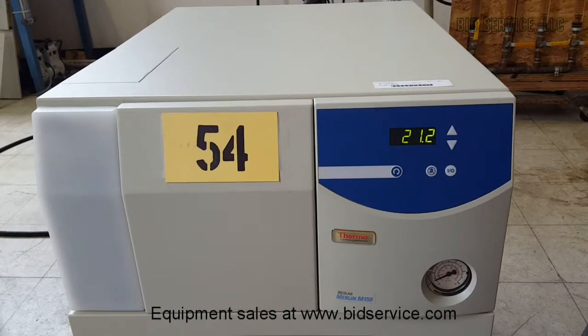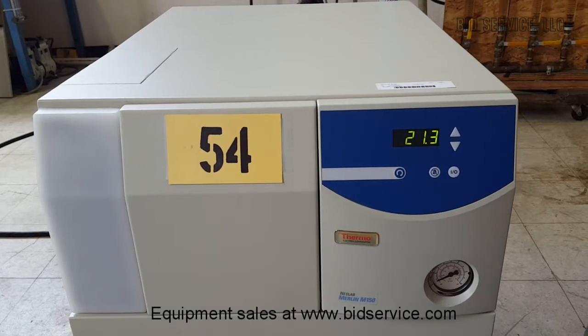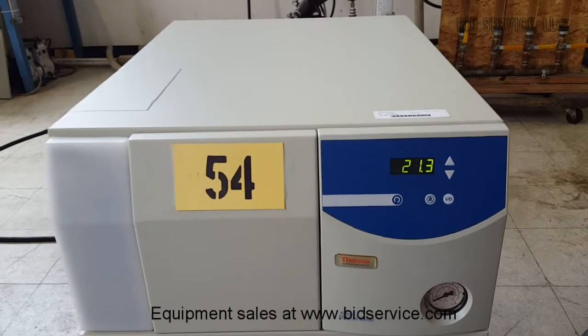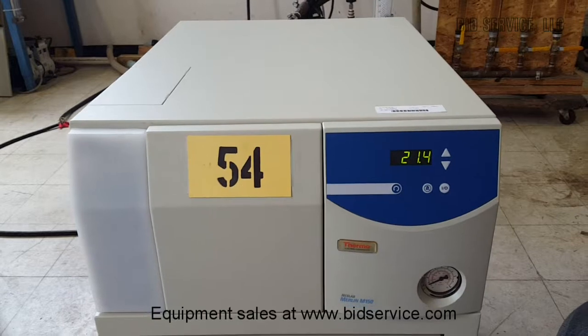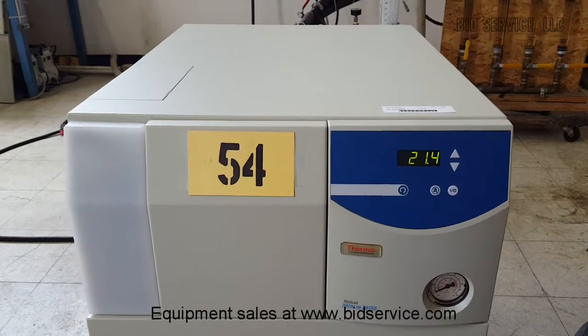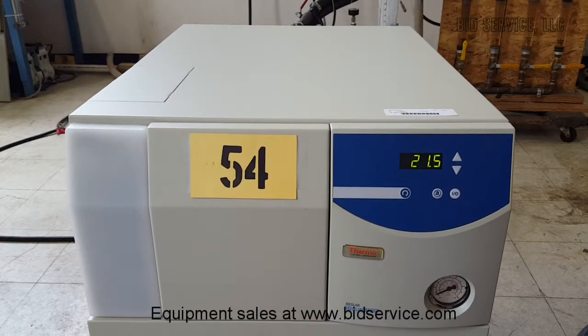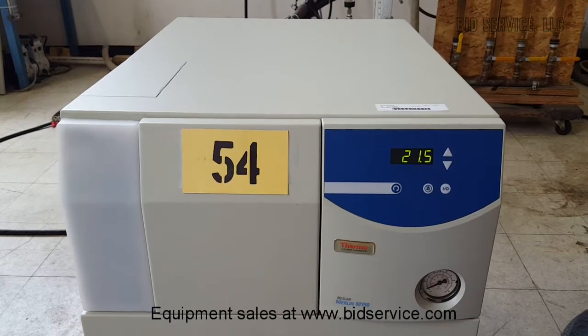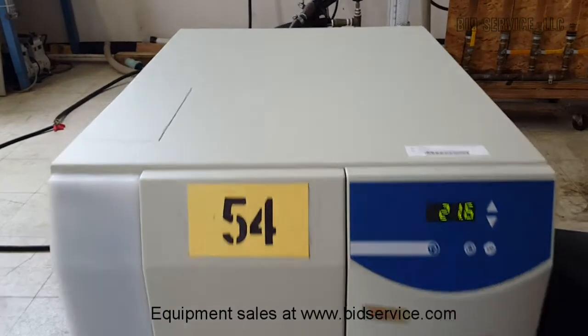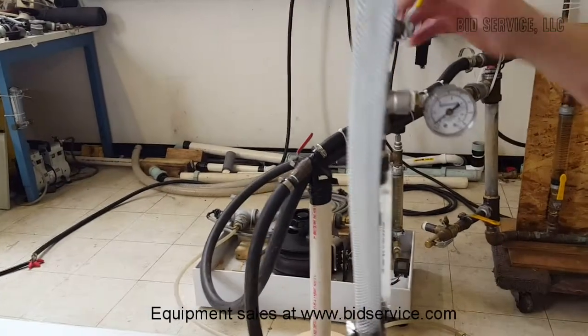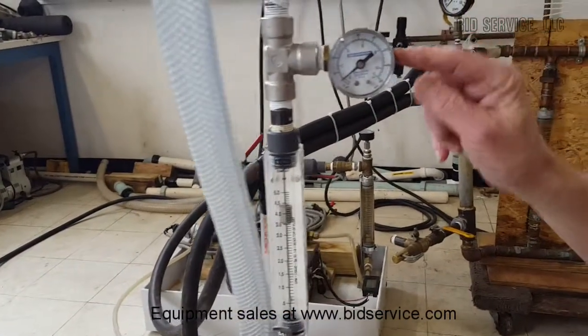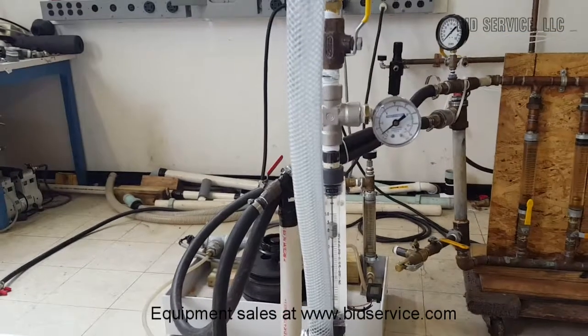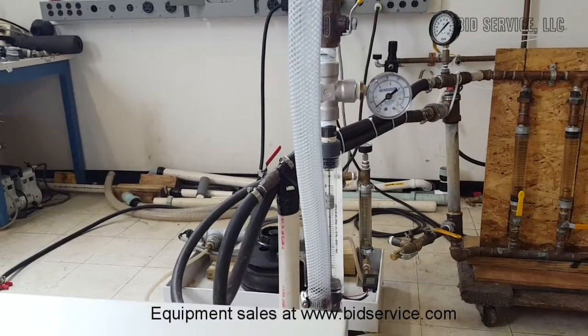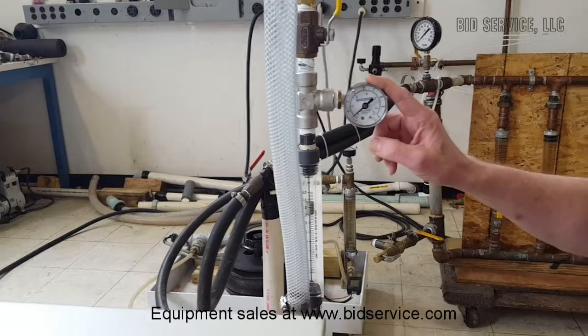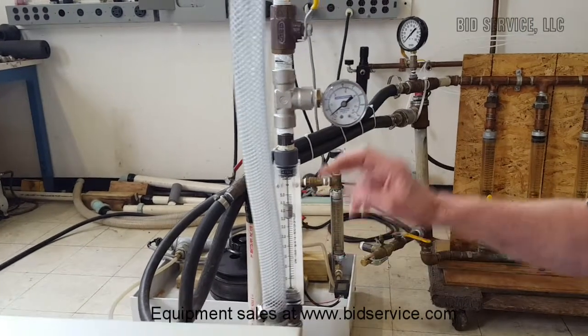So while we're waiting for it to go up in temperature, it is rated for 3.5 gallons, 3.5 gallons at 50 psi. So what we'll do here is I'm going to take this and throttle this down, and that's another thing that we like to do. Normally these analog gauges are pretty accurate, but just to make sure, we always put our own gauge in and our flow meter as well to make sure.